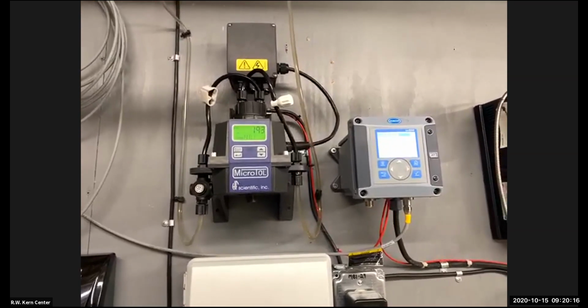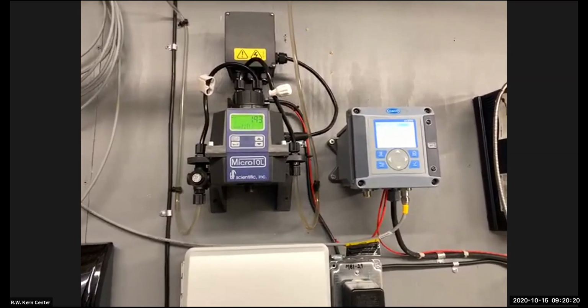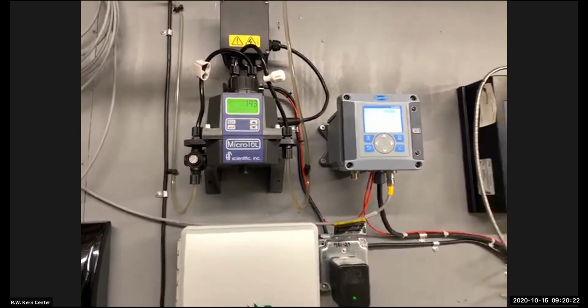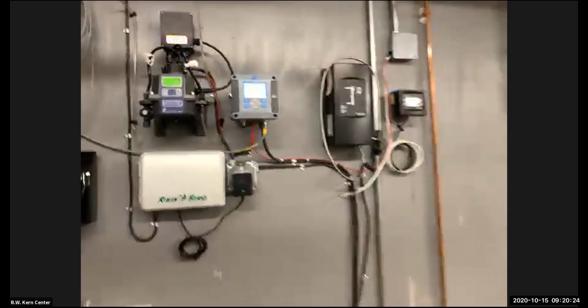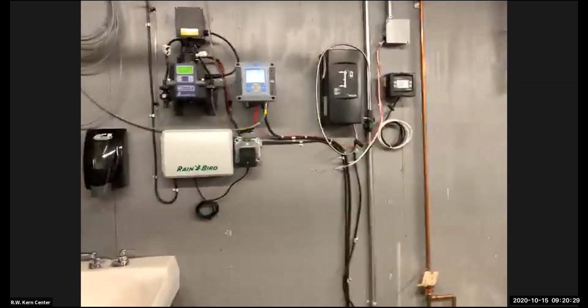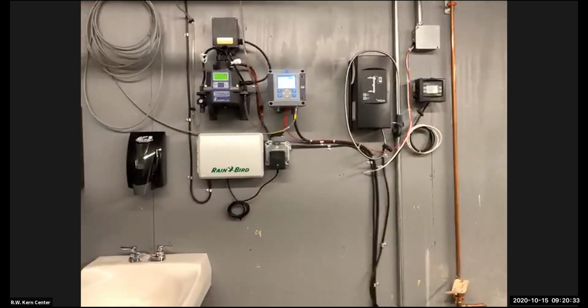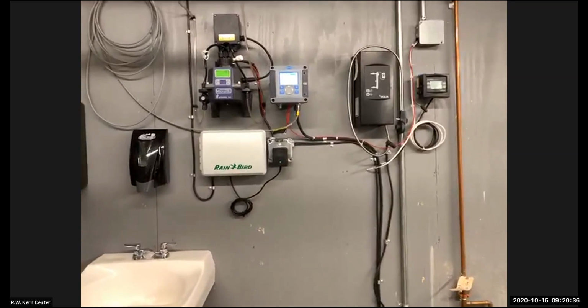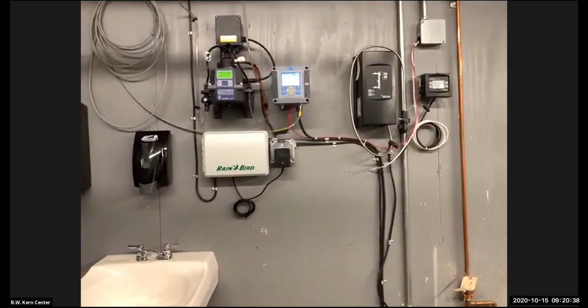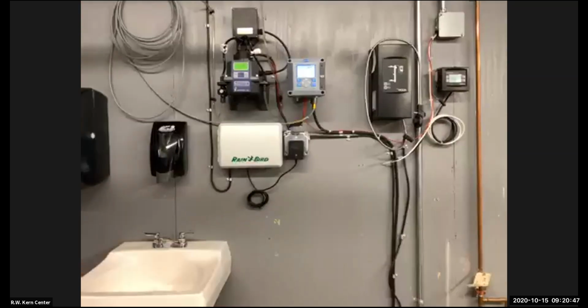The most important of those is periodic bacterial testing, the presence or absence of fecal coliform bacteria in our finished water. If that is present, it means that we have a serious public health emergency and that things need to get shut down. That is basically telling us, is our treatment working on the basic fundamentals? But then there are another set of water quality indicators that we need to keep track of and have certain limits which we cannot exceed.